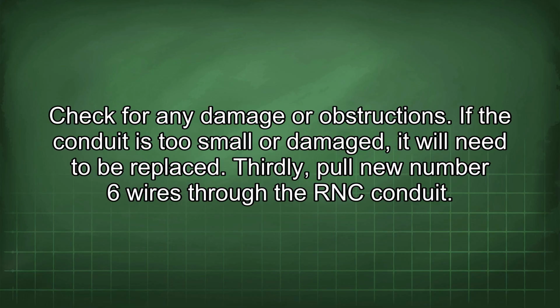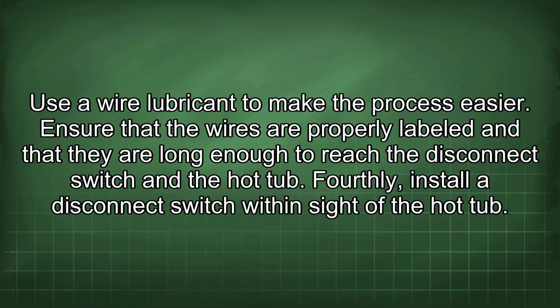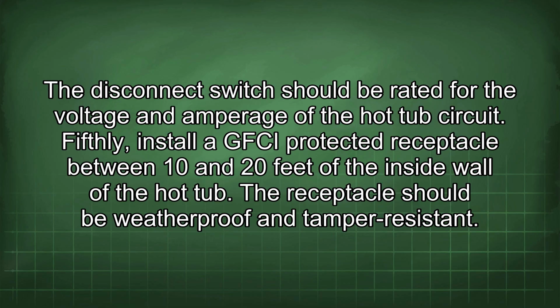Thirdly, pull new number 6 wires through the RNC conduit. Use a wire lubricant to make the process easier. Ensure that the wires are properly labeled and that they are long enough to reach the disconnect switch and the hot tub. Fourthly, install a disconnect switch within sight of the hot tub. The disconnect switch should be rated for the voltage and amperage of the hot tub circuit. Fifthly, install a GFCI protected receptacle between 10 and 20 feet of the inside wall of the hot tub. The receptacle should be weatherproof and tamper resistant.